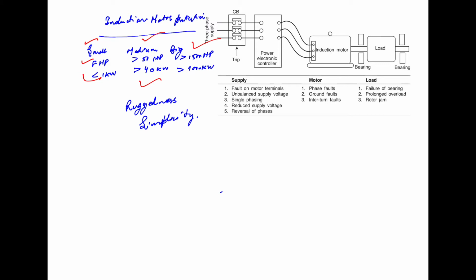Now, however, it is not possible to make any general statements about the protection of induction motors, since the protection scheme depends upon the size of the motor. Size means the horsepower or kilowatt rating of the motor, and its importance in the system. That is why induction motor protection has not been standardized to the extent that other protection schemes have been. However, whatever protection we may provide, all the motors, big or small, are subjected to similar faults and abnormal operating conditions. So we can discuss that.